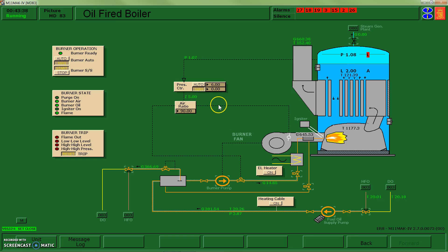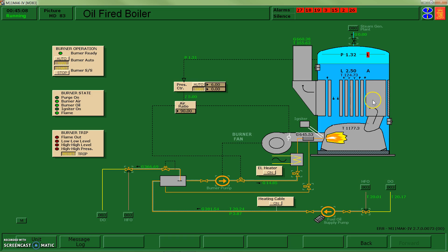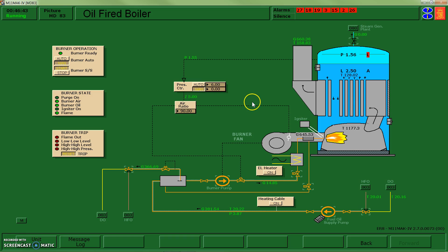At this point you might question why don't I heat it up faster, could have saved ourselves some time. Well, part of the idea of heating up the boiler is we want to do it slowly so all the metal has a chance to expand or contract at the same time. We don't want to warp, bend, crack any tubes. So our safest way to start up a boiler is almost always going to be as slow as possible. Sometimes we might even stop the burner, let it sit for five or 10 minutes during the start up in order to allow it a bit of extra time to equalize.